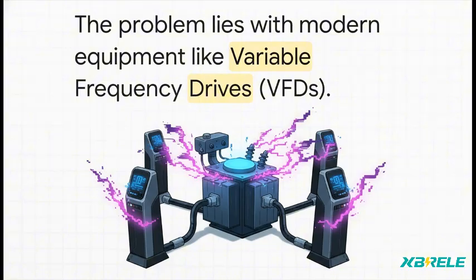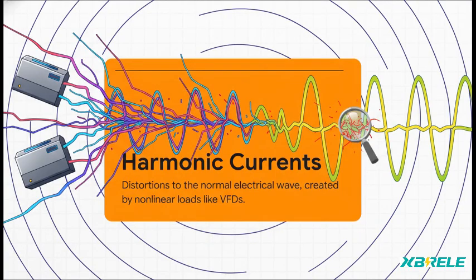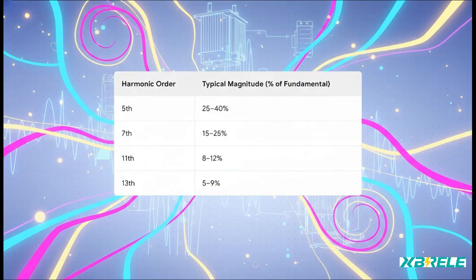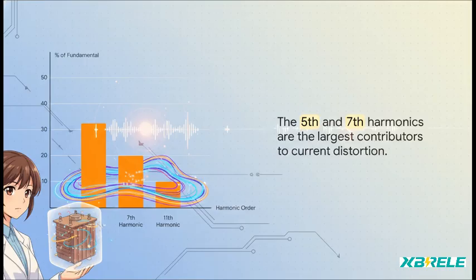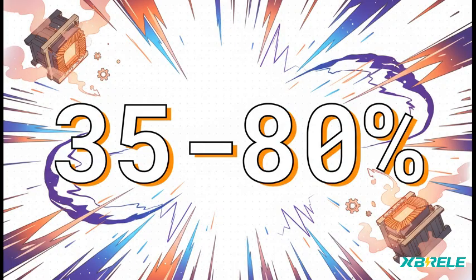The culprit? It's often hiding in plain sight, your variable frequency drives, or VFDs. See, these VFDs generate what's called dirty power, or more technically, harmonic currents. And it's not random. A standard VFD actually creates a pretty predictable pattern of these harmonics. But what's really key here are the 5th and 7th harmonics. They're the biggest troublemakers. We're talking about total harmonic distortion that can hit anywhere from 35 to 80%.